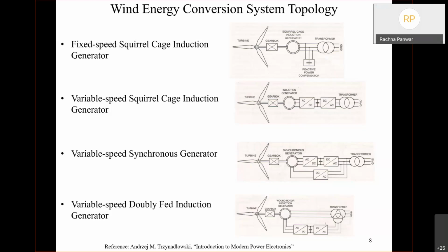Yeah, so basically we want to play with the slip power. Either we want to extract the slip power in one case, or in another case we want to inject it. In which case do you want to extract the slip power? Tell me directly: subsynchronous mode or supersynchronous mode? This is for the generator. In which case do you want to extract power from the rotor?